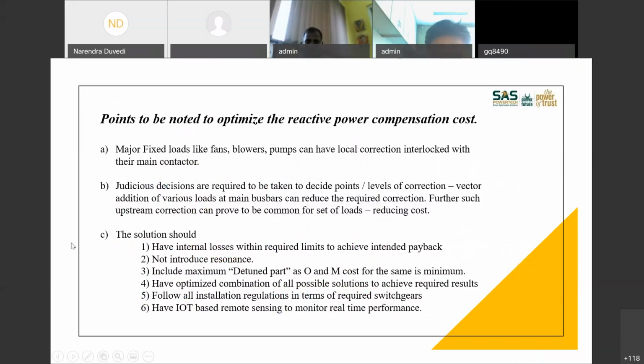Points to be noted to optimize the reactive power compensation cost. Whatever we discussed so far, let us try to summarize it. Major fixed loads like fans, blowers, pumps. See, a lot of industries have large induction motors which work either only on DOL or star delta starters, and their loads are, say, constant always. I mean, the loads do not change much.